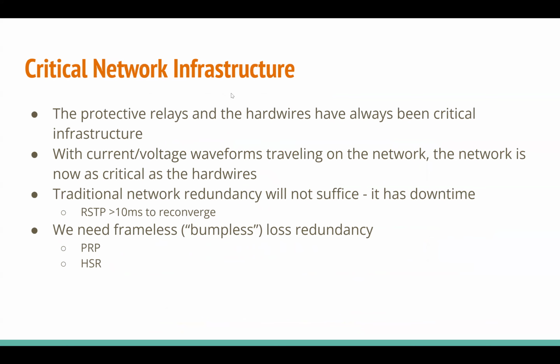So the point on this slide is that we have methods of making sure our Ethernet-based networks will not go down. We have a couple of different options. The older method is RSTP, but the problem with RSTP for network healing is that it takes time to heal, and protection cannot go offline, or the utility will absolutely be losing money. With RSTP for network healing, if your Ethernet network had a fault, you'd be down for about 10 milliseconds, which doesn't seem like a lot, but that's unacceptable, so we need to do something better.